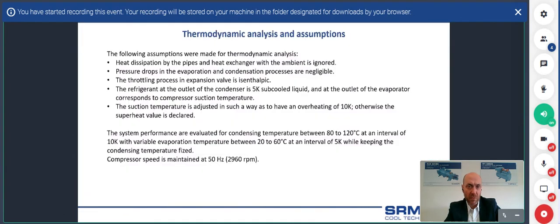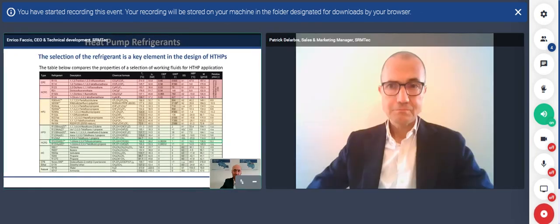We are of course investigating. What is important is to check the behavior of the refrigerant. Coming back to my presentation, to the table representing the list of suitable refrigerants, one very interesting and promising result is the 1336 refrigerant, which has a higher critical temperature at a suitable critical pressure. The first investigation indicates that this refrigerant is also very promising. So in the next months we will have some testing sessions with this new refrigerant, and quite soon we will come back with another webinar or presentation to show the results.